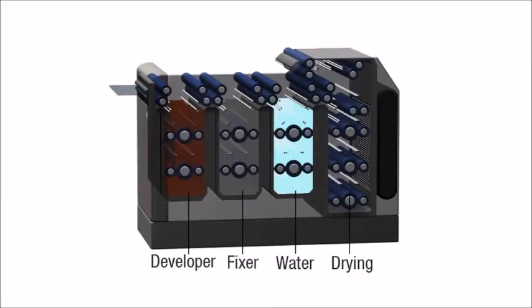In an automatic system, there are four steps in the processing of a radiographic image. Developing converts the silver ions within the crystal structures into a metallic silver form by delivering additional electrons to the silver ions. Fixing: fixative chemicals flush the remaining unexposed and underdeveloped silver halide from the film and stiffen the gelatin so that the visible image is preserved for archiving.